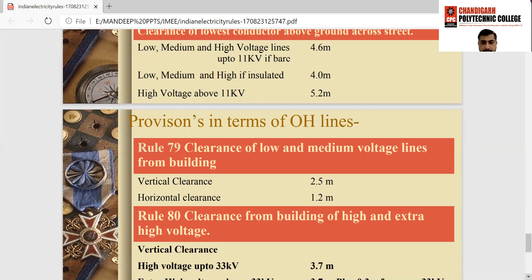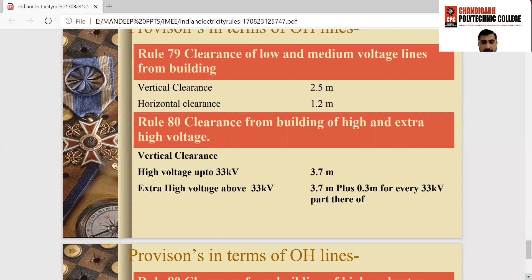The vertical clearance for high voltage or extra high voltage up to 33 kV, the minimum clearance from building required is 3.7 meter. And for extra high voltage above 33 kV, the minimum clearance required is 3.7 meter plus 0.3 meter for every 33 kV or part thereof. If the voltage increases from 33 kV to 66 kV, then the minimum clearance required is 3.7 meter plus 0.3 meter. It means for 66 kV, the minimum clearance required is 4 meter.